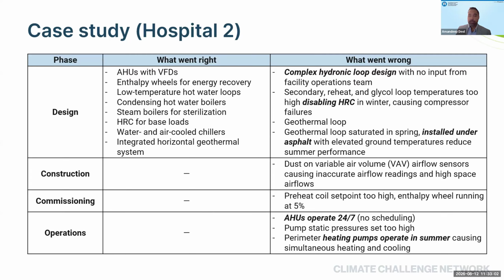The result of that gap was that nobody understood how this heat recovery chiller was supposed to be operated in that complex hydronic loop design, so the operator turned to the safe side, which was to ensure that the building was working. The way they did that was to disable the heat recovery chiller, so they were not able to recover any heat. The geothermal loop, which was supposed to provide that additional source of heating, as a sink and source, was installed under an asphalt parking lot in a way that it wasn't able to be used as a source or a sink, because it was too close and the ground temperatures were too high in that neighborhood. The geothermal loop got disabled as a result.